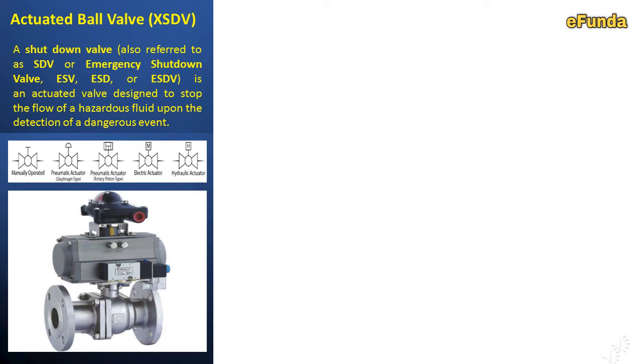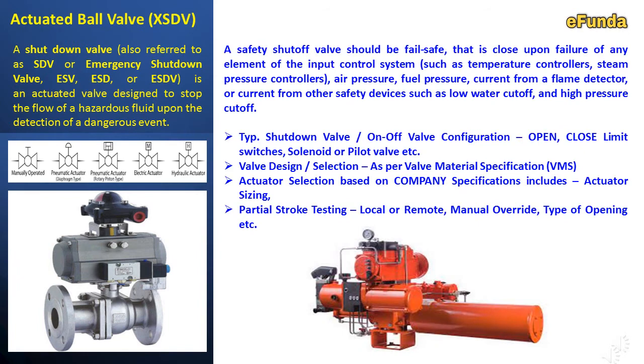A safety shut-off valve should be fail-safe, that is, close upon failure of any of the control input systems such as temperature controller, steam pressure controller, air pressure, fuel pressure, current from flame detector, or current from other safety devices to cut off.